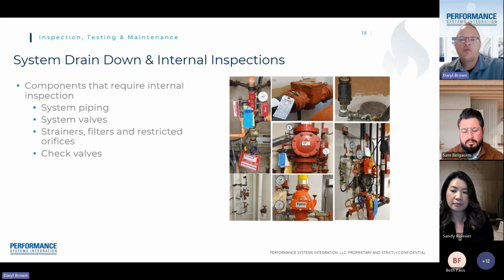A lot of this has to do with breaking down fire sprinkler components and doing internal inspections. Here you'll see some of the items that we actually do to break down. So we drain the sprinkler system down and do a visual inspection inside the piping. We're checking for anything from corrosion to any kind of mechanical restrictions.